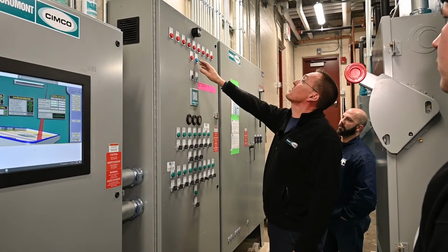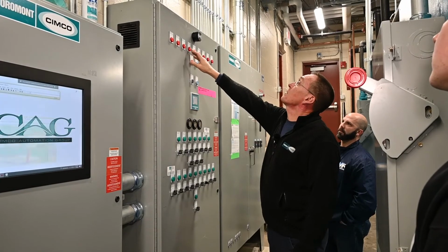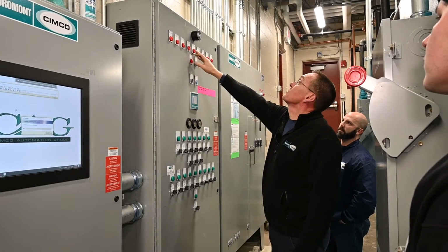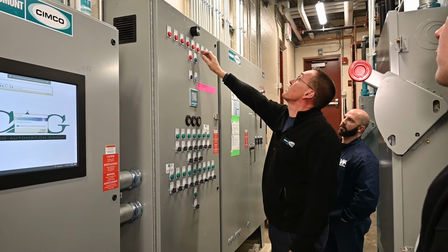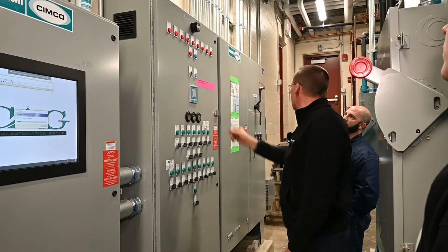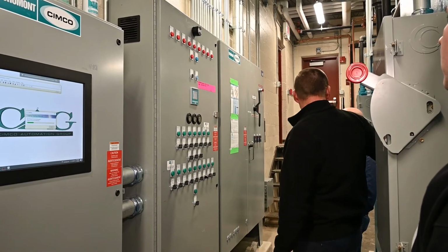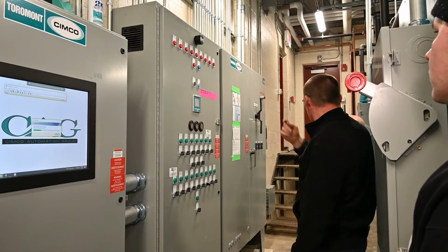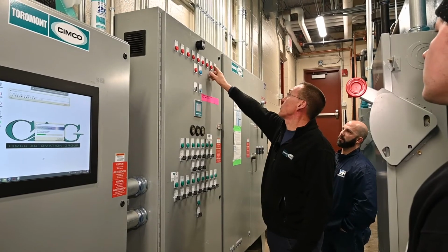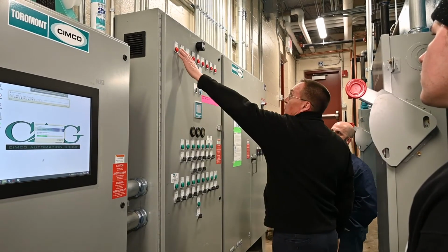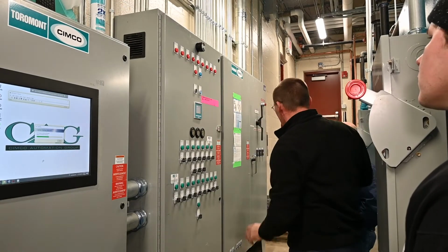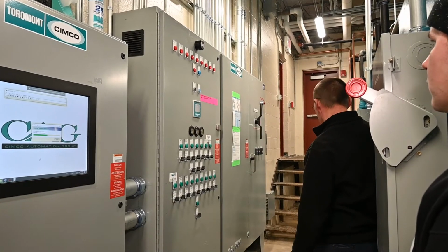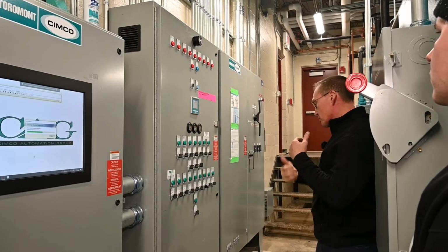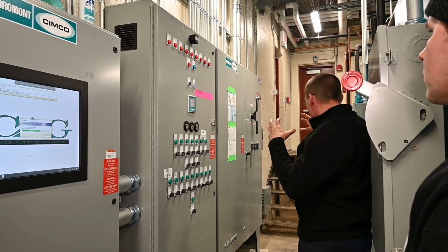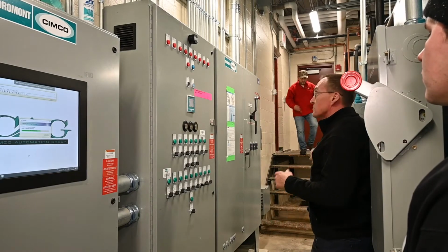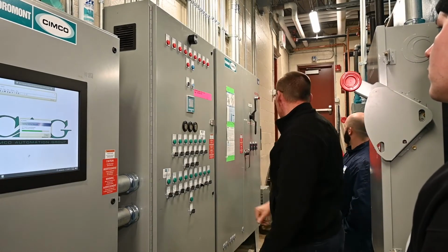If there's a problem with one of the compressors, if it's C1 on a general failure, it'll be here. General failure alarms are for number 1, number 2, and number 3. If it's a low oil level failure, which is a trigger from the low oil switch on each compressor, it would be illuminated here. Compressor low oil level 1, 2, and 3. And the module alarm is the internal module inside the motor electrical box, monitoring discharge temperature, pressures, and the motor itself of that semi-hermetic compressor. And that would be one of these 3 here, which would be illuminated.